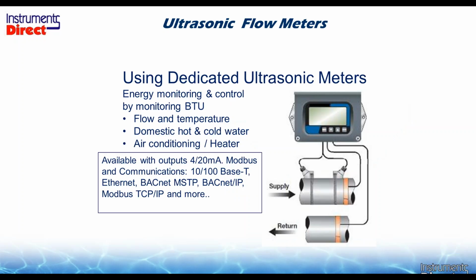Some energy studies take an extended period of time. Sometimes when we go to a university, they would say, we would like to look at the energy over the summer, so we would like to rent 14 meters for 3 months. And sometimes the economics aren't practical. With that in mind, in many cases we know that these are going to be primary metering points, so why not make the investment and buy 14 dedicated energy meters for probably the same price you're going to rent 14 meters for 3 months? In this case, we have a dedicated device, and it would read the same thing as the other flow meters, strap on RTD for the supply, strap on RTD for the return.